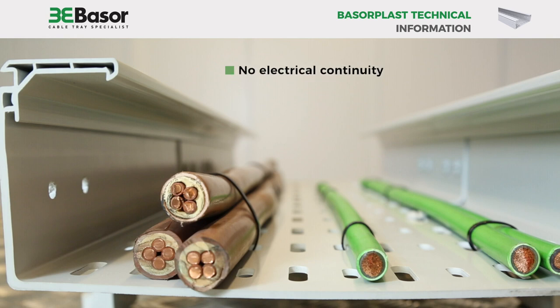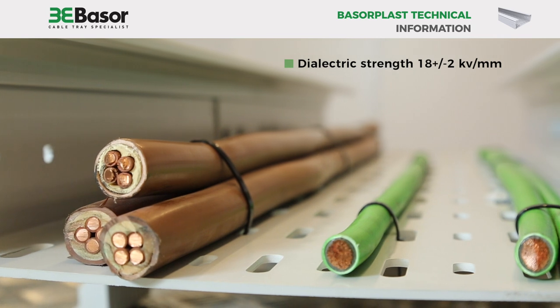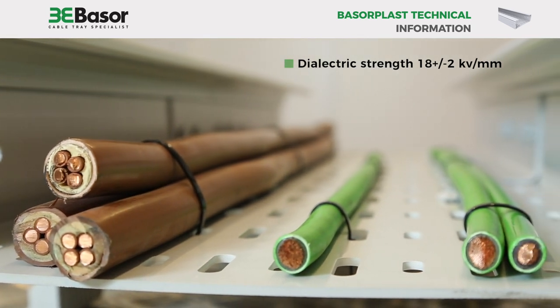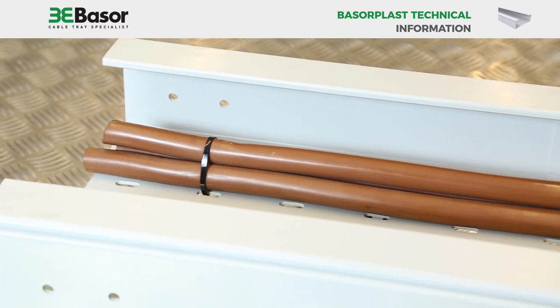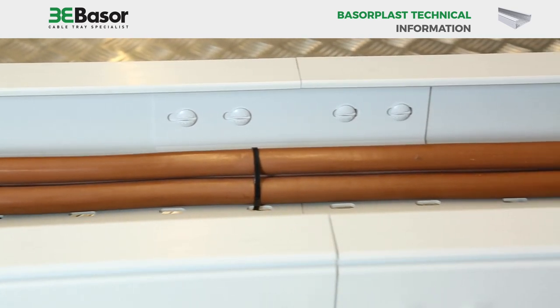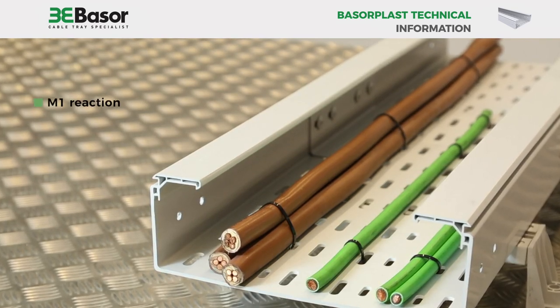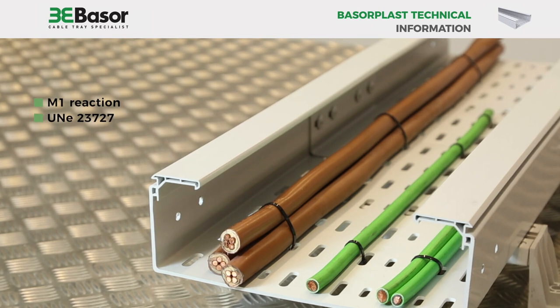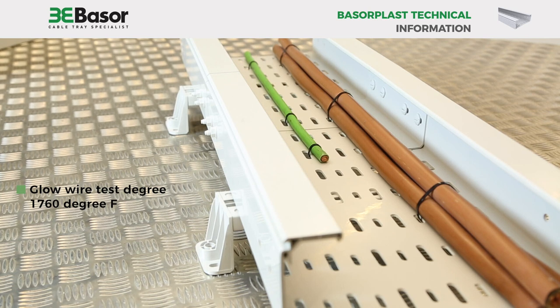It provides no electrical continuity and rather acts as a second electrical insulating component for the cables installed. It has a dielectric strength of 18 ± 2 kilovolts per millimeter. The PVC make of Basorplast provides highly protective cable support for both inside and outside applications against corrosive substances. Basorplast meets or exceeds the requirements of global fire codes and standards — it has an M1 reaction to fire according to UNE 23727, and passes the glow wire test at 1760°F.